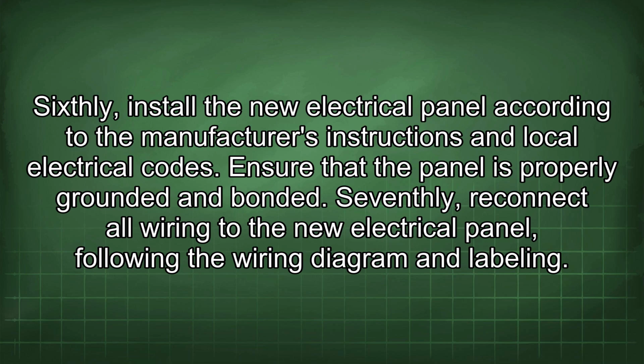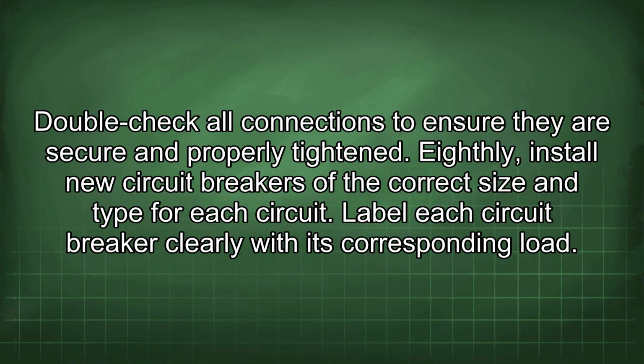Sixthly, install the new electrical panel according to the manufacturer's instructions and local electrical codes. Ensure that the panel is properly grounded and bonded. Seventhly, reconnect all wiring to the new electrical panel following the wiring diagram and labeling. Double-check all connections to ensure they are secure and properly tightened. Eighthly, install new circuit breakers of the correct size and type for each circuit. Label each circuit breaker clearly with its corresponding load.